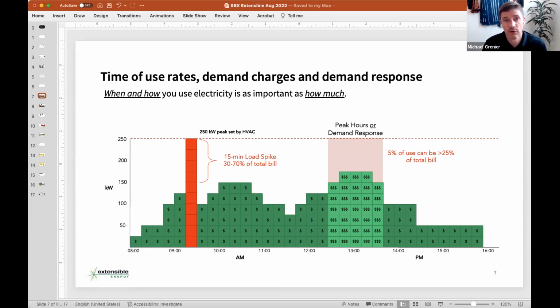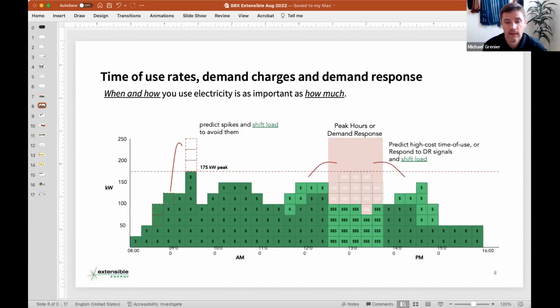If you use software, you can predict these peaks, you can see them coming. You can model the behavior of the building, you know the utility rates, and based on that, you can more intelligently dispatch what the building systems are doing. The benefit is that you move energy from one time frame to another, you lower the peaks, and you can avoid high time-of-use charge periods of the day.